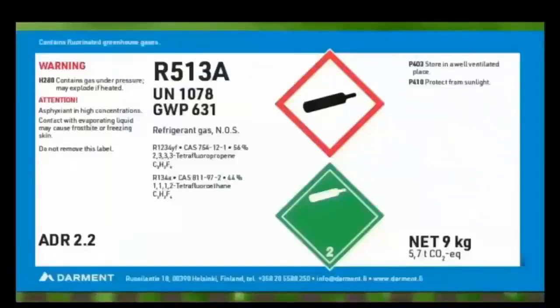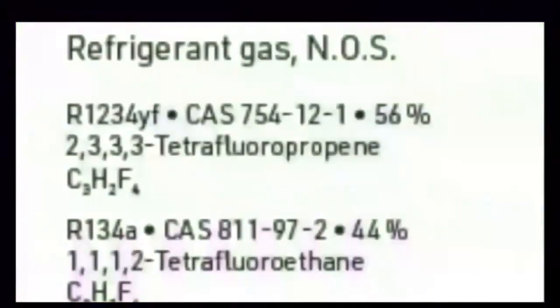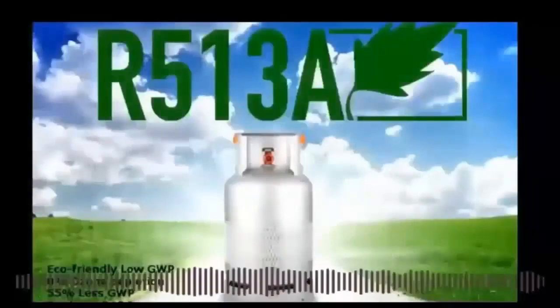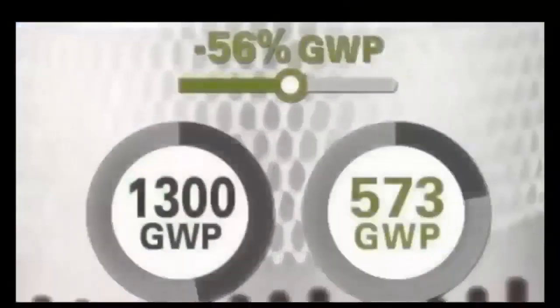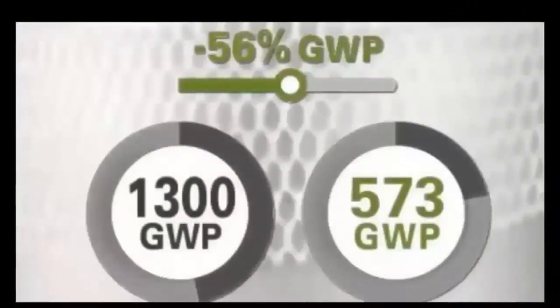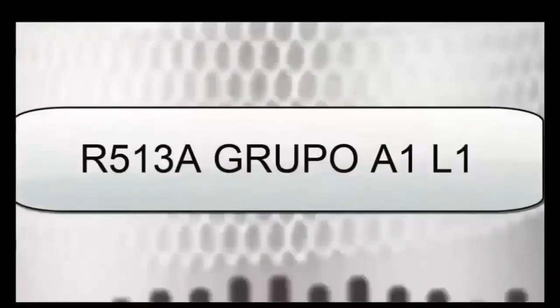R513A refrigerant is a mixture of R134a refrigerant at 44% plus R1234YF refrigerant at 56%. R513A refrigerant is a low GWP, non-flammable alternative refrigerant belonging to the A1 safety group, which allows equipment manufacturers to comply with future HFC regulations.